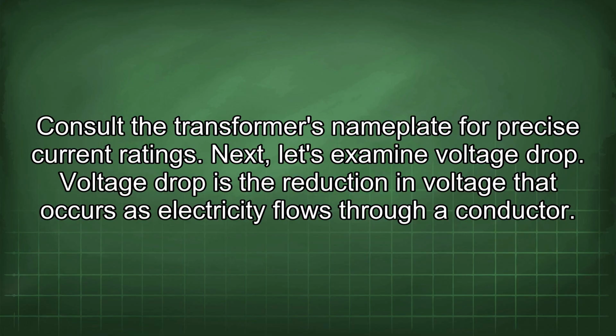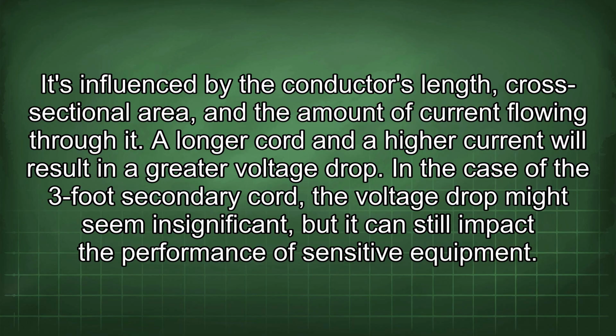Next, let's examine voltage drop. Voltage drop is the reduction in voltage that occurs as electricity flows through a conductor. It's influenced by the conductor's length, cross-sectional area, and the amount of current flowing through it. A longer cord and a higher current will result in a greater voltage drop.